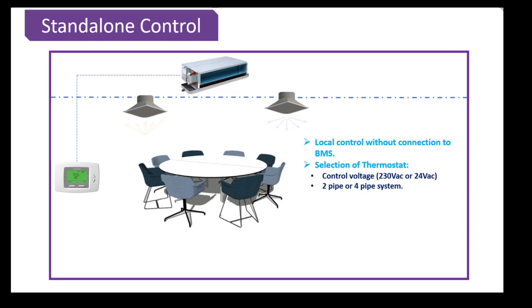A two pipe system is a heating only or a cooling only system while a four pipe system is a both heating and cooling system. So you shall keep in mind this thing while selecting a thermostat because there are different thermostats for two pipes and four pipe systems. Another very important parameter is what type of control is required for your cooling and heating valve actuators. Is it a two position floating or modulating control?